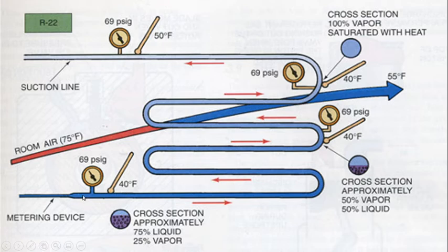As it goes to the metering device, it sprays a little bit of refrigerant in here. The refrigerant breaks down between somewhere in 75 to 25 or 80 to 20 liquid and gas. So it's going to be 80% still liquid, but the gas is going to be flashed off. It's going to be considered flash gas because it goes into a bigger area. So automatically it's going to expand. As this liquid is running through this coil, it is taking a few BTUs off the 75-degree air.